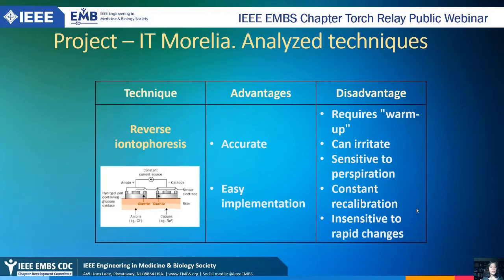One of the analyzed techniques was reverse iontophoresis. This technique consists of injecting a constant current to the skin through electrodes that contain an enzyme that reacts to glucose levels. This method has the advantage that it's accurate and it has an easy implementation. However, it requires warm-up and it can irritate the skin. Besides, it is sensitive to perspiration and needs constant recalibration. Furthermore, it is insensitive to rapid changes in glucose levels.